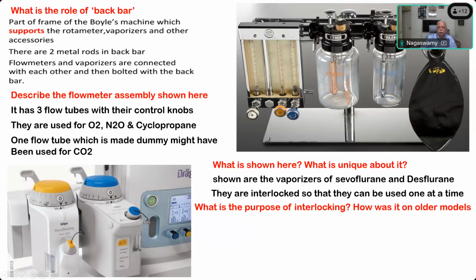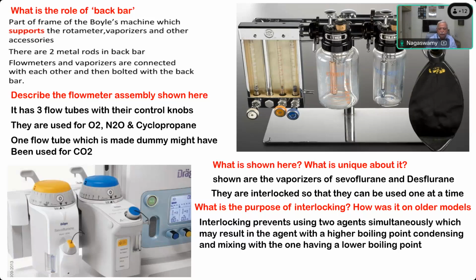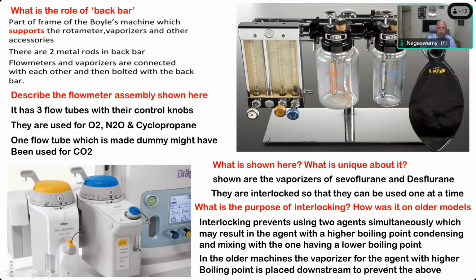So in order to prevent that, in older machines, they always had the agent with a higher boiling point downstream and the agent with a lower boiling point upstream. Similarly, interlocking is to prevent the condensation of one agent into the other vaporizer and causing output which you cannot measure. That is the problem. So interlocking prevents using two agents simultaneously, which may result in the agent with a higher boiling point condensing and mixing with the one having a lower boiling point. And in the older machines, the vaporizer for the agent with a higher boiling point is placed downstream to prevent the above problem. So trilene had a higher boiling point, so it is always to be attached only after the halothane vaporizer, which is called the downstream position. So that is the answer for it.